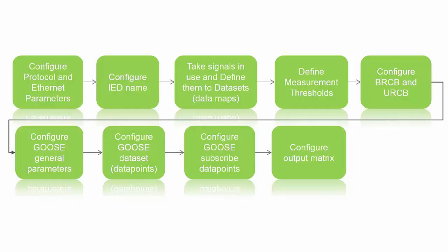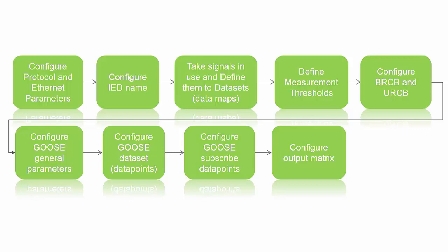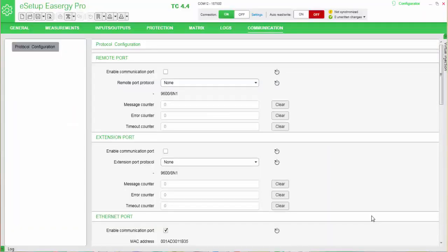So what we need to do, we need to configure protocol and Ethernet parameters, we need to configure IED names, we need to take into use signals which we are going to use, we have to define them for the datasets, we preferably will define measurement thresholds so we can limit the activation of the measurement in case of small changes. We will configure buffered report control blocks and unbuffered report control blocks, we will configure the GOOSE publishing parameters, the GOOSE subscribing parameters, we will configure the output matrixes. After that it is possible to do testing and analyzing with, for instance, Wireshark analyzing tool.